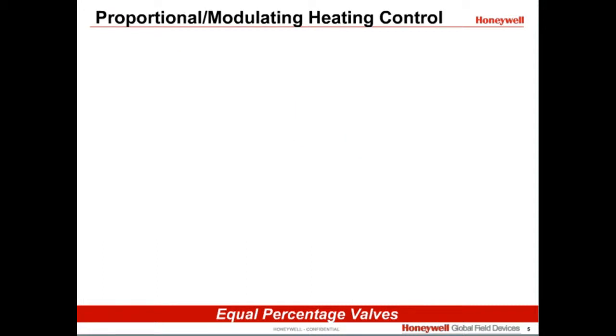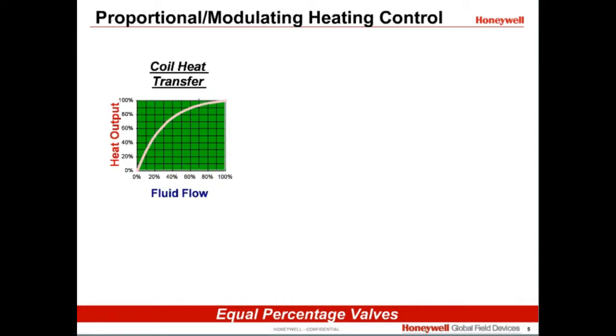In modulating systems, the goal is to have the heat output of the system vary directly with demand from the controller or thermostat. Most heating coils in HVAC applications have a heat transfer characteristic that is similar to this one. You can see how it transfers a large amount of energy as the valve cracks open. Then, as the valve opens further and further, the rate of energy transfer tapers off. It would be difficult to control this space accurately.